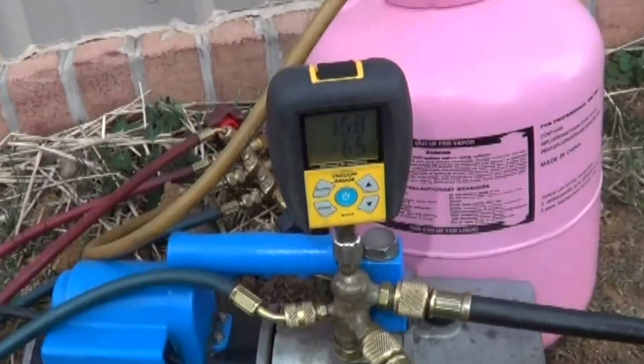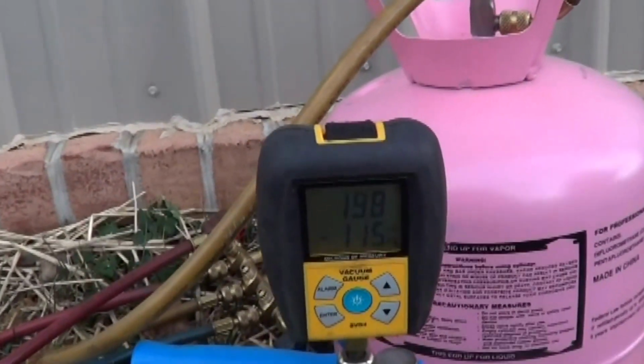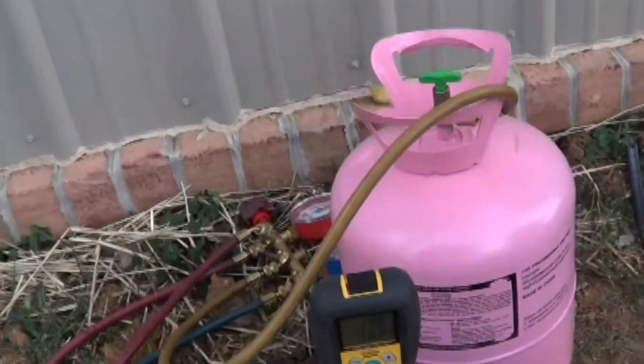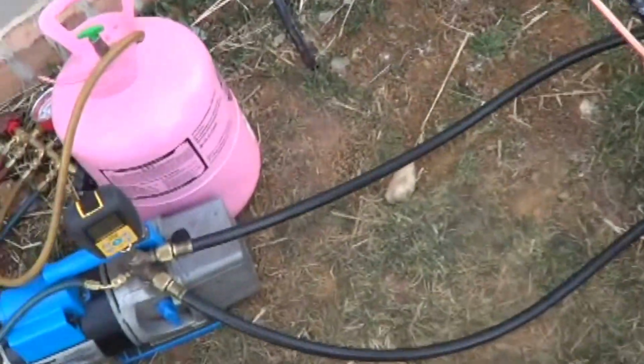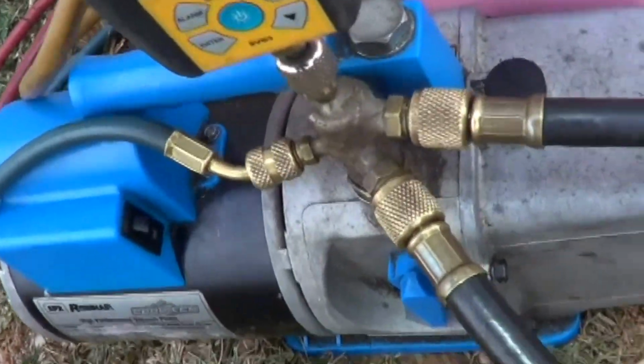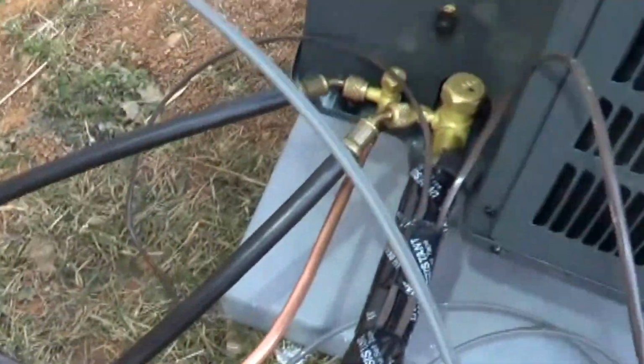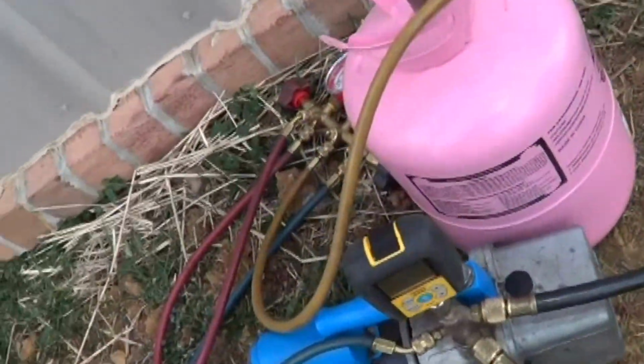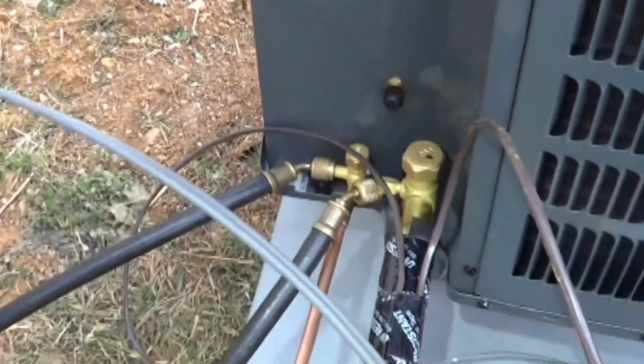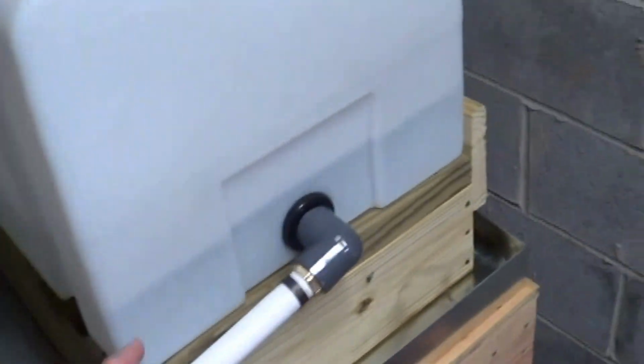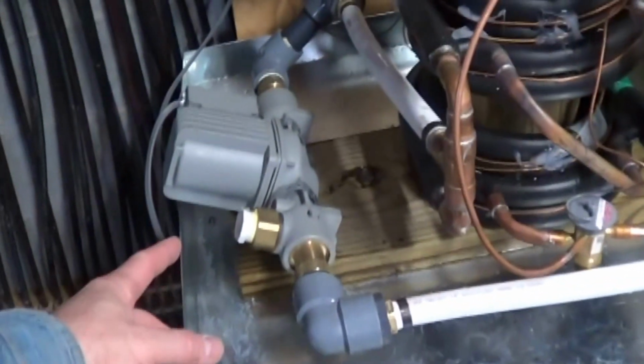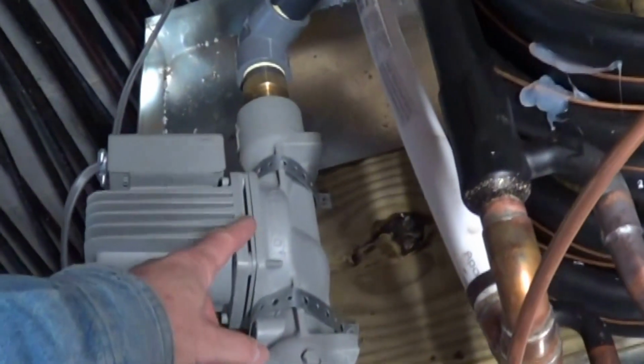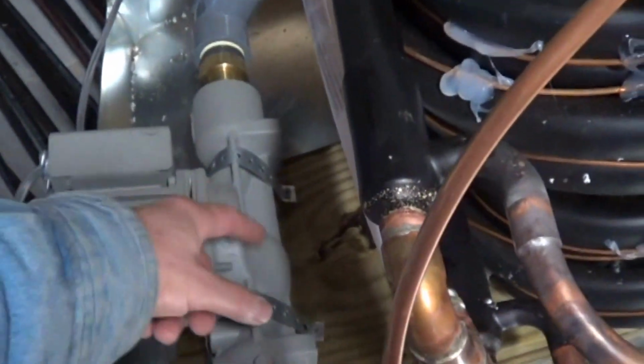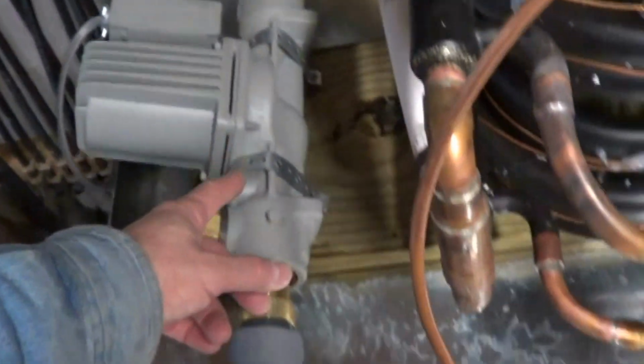Here's the third vacuum. You can see about 150 microns. I use a vacuum manifold with 3/8 hoses. So if it's 150 microns here, it's probably 300 microns right there. I had to raise the tank up here to get the pump to self-prime. Also mounted the pump sideways. It primed a lot easier.